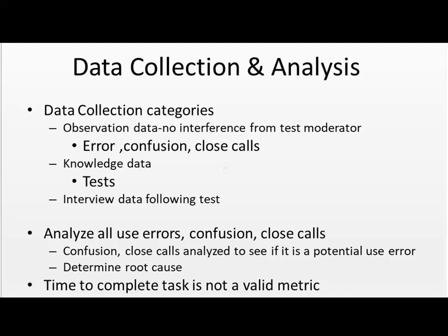Now, it's an important point that the time to complete a task is not a valid metric. You cannot have a criteria where if the person completes the use of the device within X minutes, that's a success. That is not a valid metric.